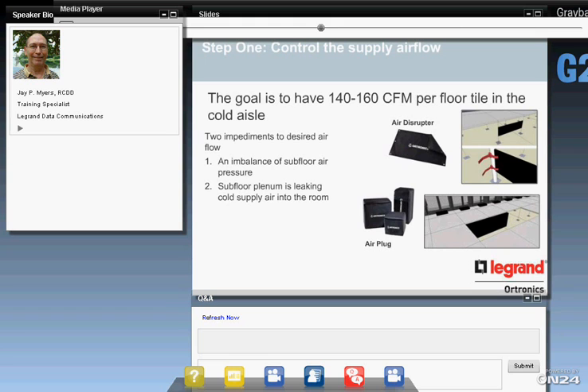So first step, every data center I've ever walked in has holes in the floor where holes have been cut for cabling, or the cabling's been removed, and we need to plug those holes up. There in the center you see where it says air plugs. Those are just squishy little cubes. They're covered with flame retardant canvas. They're rated for plenum areas. So we can go around and squish those into those holes and just plug them up. In the past, we and many in the industry have used brushes to help seal those, and those work somewhat. They're better than nothing, but they really don't seal very well around cables. These conform very well and really plug up those holes.